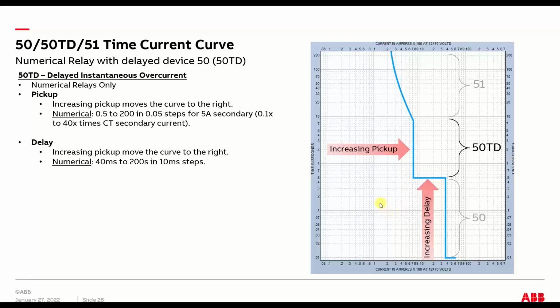So with all the same terminology, one of the advances that almost all numerical relays have now is this added piece that you can add to a typical overcurrent, which is sort of a time-delayed element. It's sort of a time-delayed instantaneous. Some people call it a 50 TD, but it allows you to have a true instantaneous plus a delayed instantaneous, and then a time overcurrent, which is inverse time.